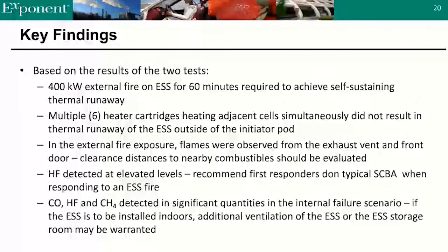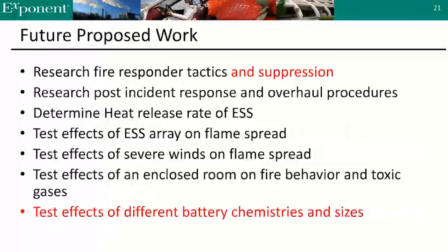There were some key takeaways from these tests. In the external fire, we got a self-sustaining fire that led to significant thermal runaway. In the internal fire, we did not get thermal runaway outside of where we initiated the fire. But in the external fire exposure scenario, we had significant flaming from outside of the energy storage system cabinet, and we knew from that clearances to nearby combustibles was something we needed to understand further. We also, in both tests, detected elevated levels of different toxic gases, and that allowed us to give some additional guidance to the fire department community in how to respond to these types of fires.